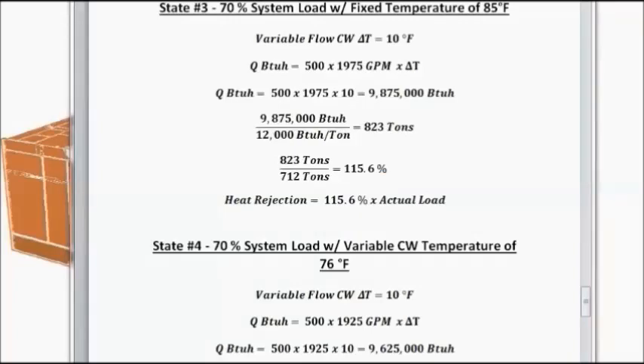In state 3, we made a significant change and dropped the load to around 70%. And we see a significant change in flow rate with the condenser water temperature maintained at a 10 degree delta T. So, we can calculate the heat rejection as a percentage of the total load. And we see this drop.